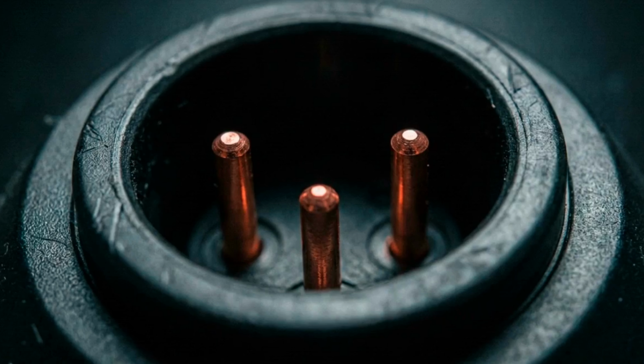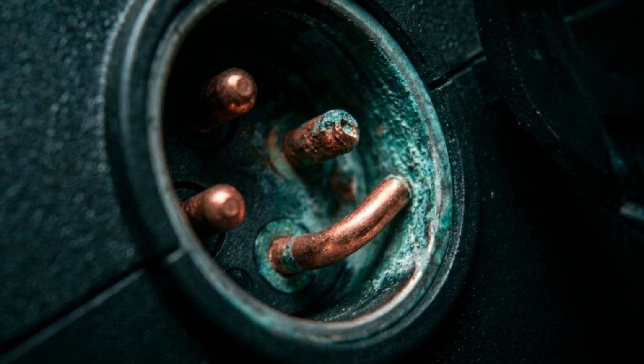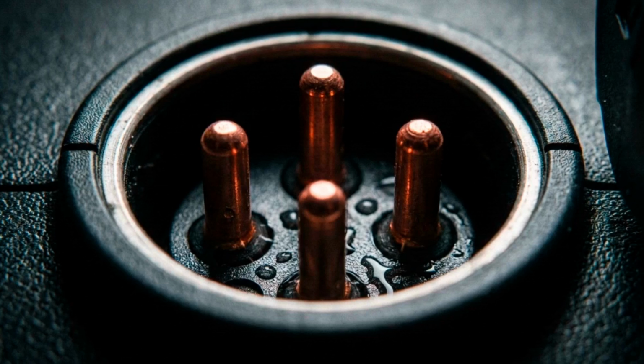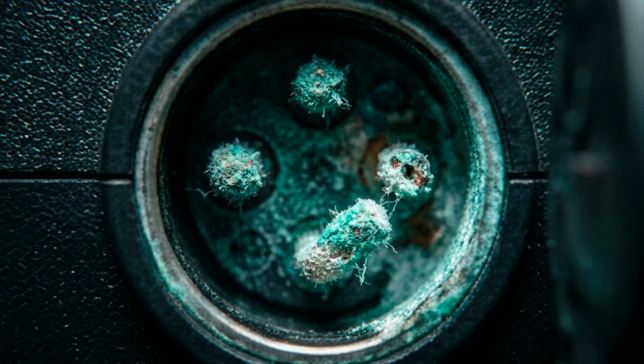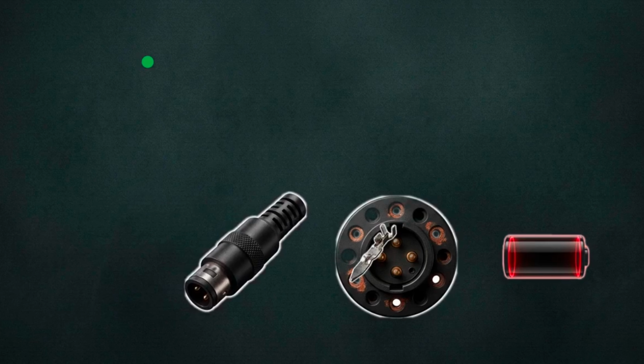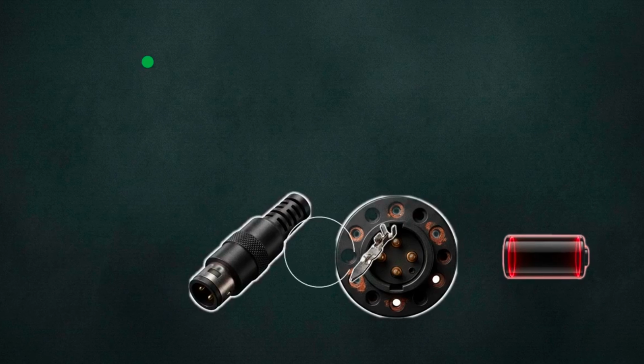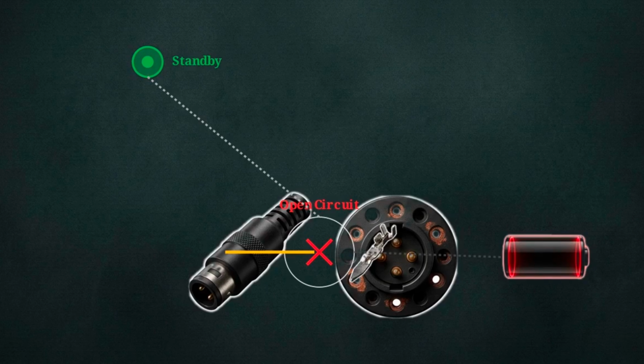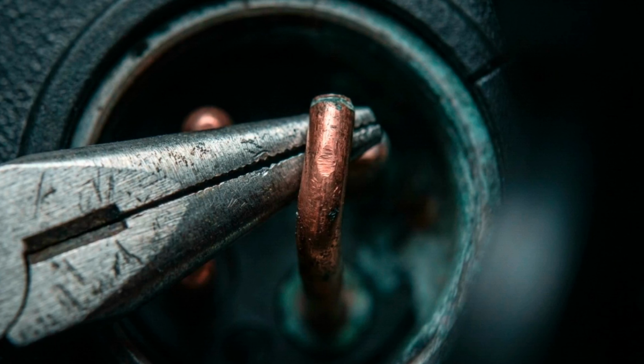Look closely inside the port. Check for bent center pins, lingering water droplets, or greenish corrosion built up from riding in the elements. When a bent pin physically misses the contact, the circuit remains open. The charger's LED stays green because it cannot electrically see the battery to deliver the current. A minor, fixable physical misalignment, right here at the port, is frequently the true culprit behind what looks like a totally dead battery pack.